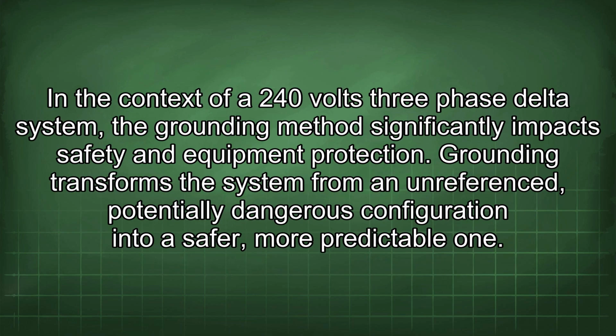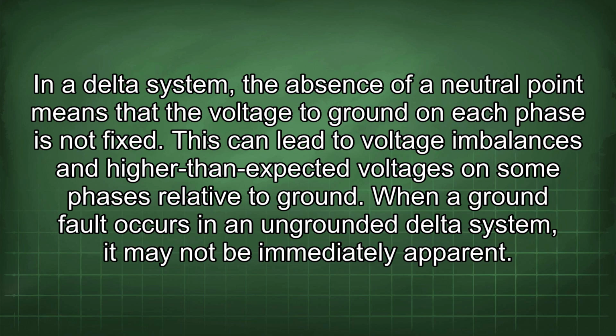In the context of a 240 volts three-phase delta system, the grounding method significantly impacts safety and equipment protection. Grounding transforms the system from an unreferenced, potentially dangerous configuration into a safer, more predictable one. In a delta system, the absence of a neutral point means that the voltage to ground on each phase is not fixed. This can lead to voltage imbalances and higher than expected voltages on some phases relative to ground.